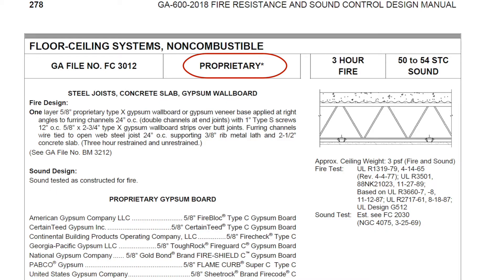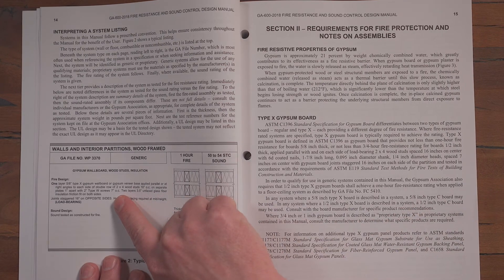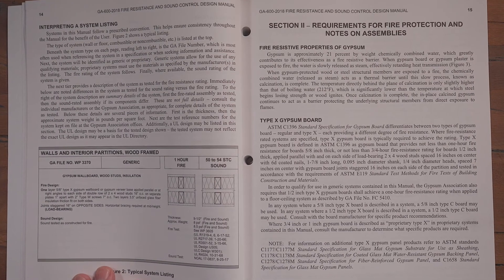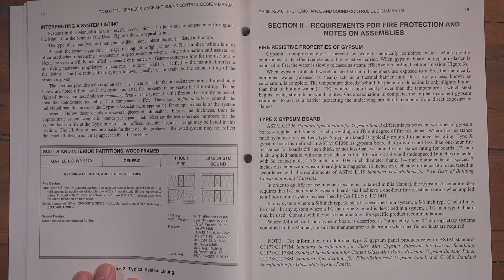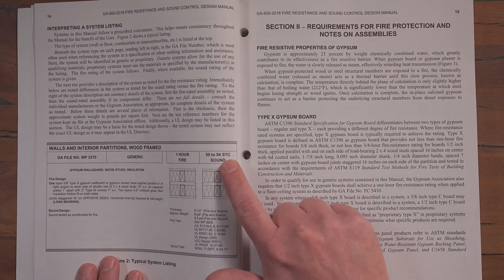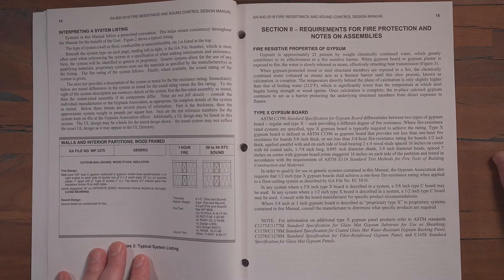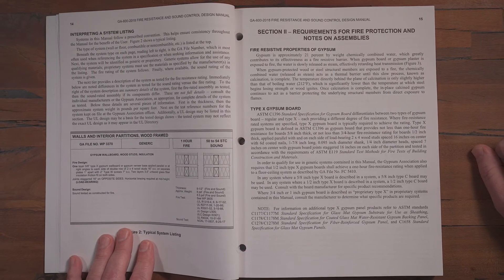Where the word proprietary appears in system descriptions, one or more of the system components is considered proprietary. Each proprietary system shall be built using the components specified by the company or companies listed under the detailed description for that system. System descriptions included in the GA600 manual are summaries. They begin with the material side exposed to the fire test and method of attachment, followed by a description of framing members and methods of installation. Finally, the unexposed side and its method of attachment is described. The fire rating, sound rating, and detail of assembly are also provided along with the thickness and approximate weight. Review the test report for complete information. Request fire or sound tests for generic systems from the Gypsum Association; proprietary test data is available from the manufacturer.